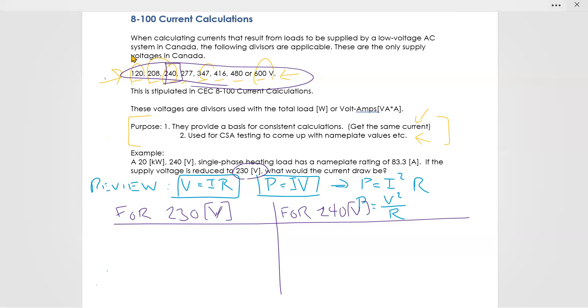Now this is not to code. It is not to code for section 8 rule 100 current calculations because you have to divide by a standard voltage, which is 240 in this case. So I am saying, what would the current draw be? Let me read the question. A 20 kilowatt, 240 volt, single phase heated load has a nameplate rating of 83.3 amps. If the supply voltage is reduced to 230, what would the current draw actually be?